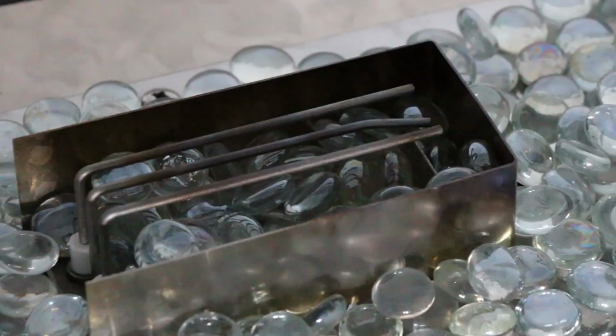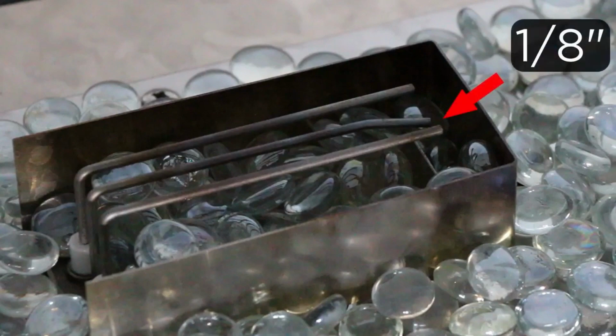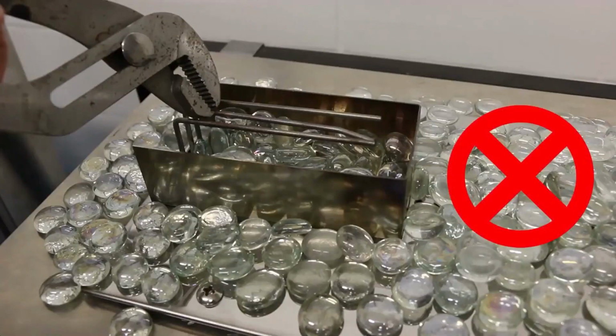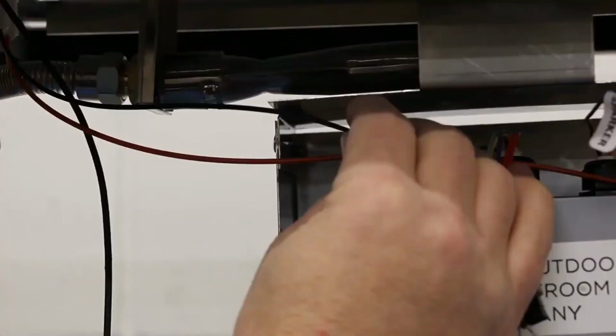The gap between the igniter and the ground wire should be approximately 1/8 of an inch. Too large of a gap and the spark may not jump between those rods. Too short of a gap and the spark may be so small that it is not hot enough to ignite the gases. Don't try and adjust the long sections of the rod as it could fracture the ceramic insulation and cause further failure. If you still hear the spark but do not see the spark, it is likely the spark is occurring elsewhere in the system.